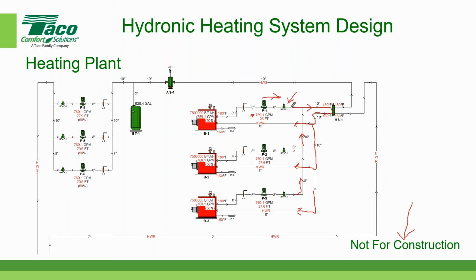So the multi-purpose valve does three functions. It's a check valve. It's also an isolation valve. You can use it to shut off the flow, and it's also a balancing valve, so you can use it to balance. So especially in a constant flow system like this, you're basically going to turn the valve to get the exact flow that you're looking for, in this case, roughly 770 gallons per minute. So those are all the components. Not every component, like I said, is shown here. There is an isolation valve shown on the boiler. On the discharge side of the boiler, we typically would have another valve on the suction side of the boiler, so you could isolate and service the boiler, those kinds of things.